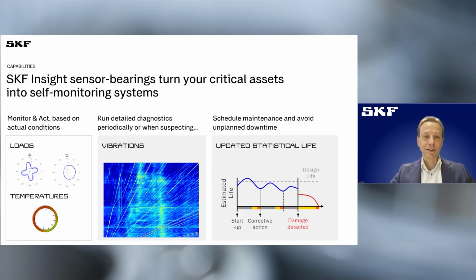Next to it, right next to it, you see almost a circle, circular axial load, but it has an offset, and this is coming from an unbalance. So it's a way to detect unbalance in the system.